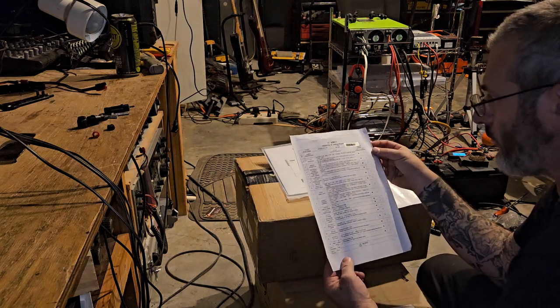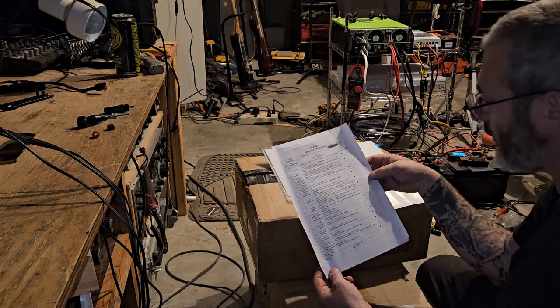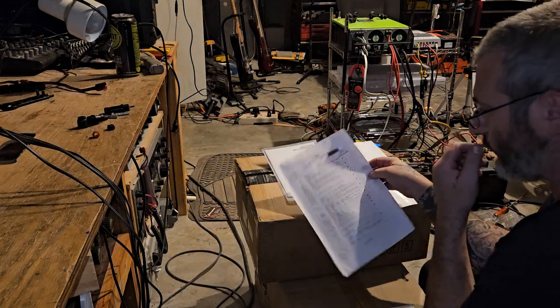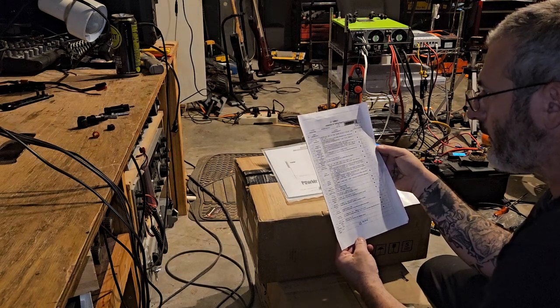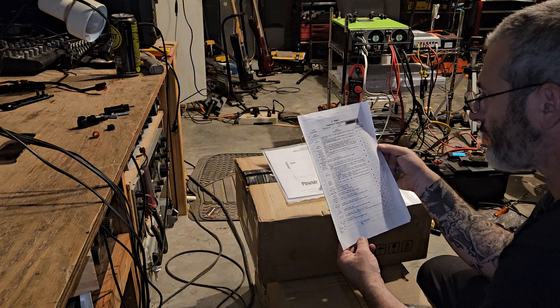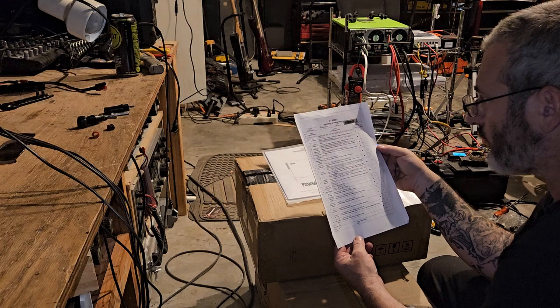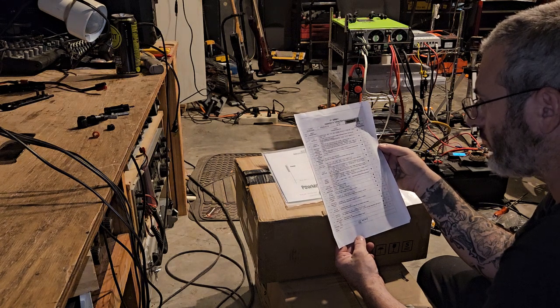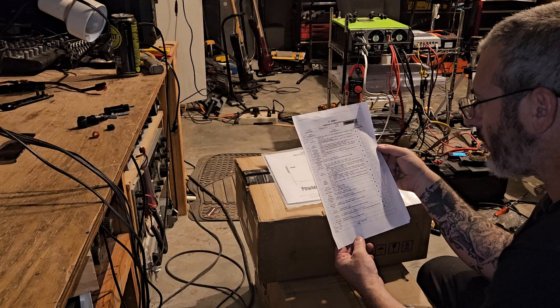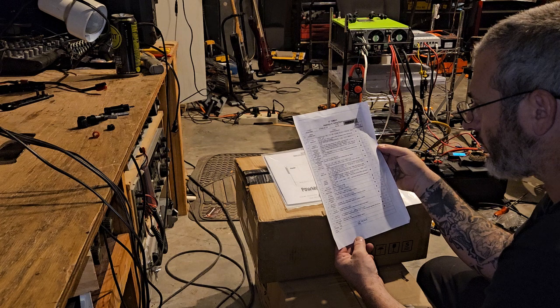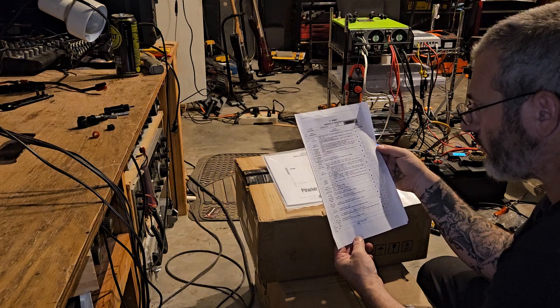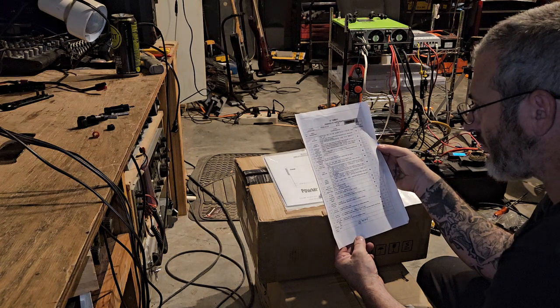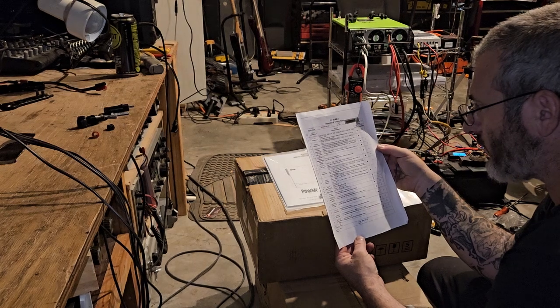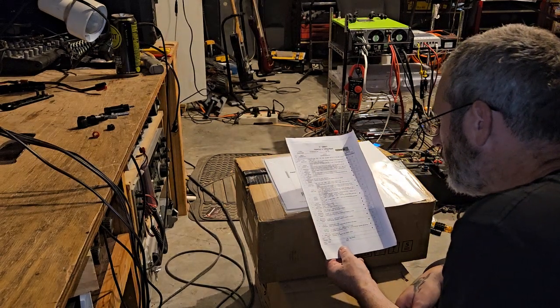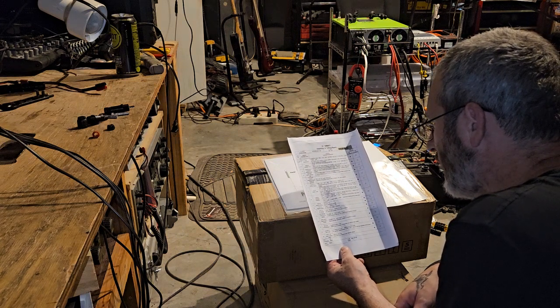They give you this inspection and testing report, and I never got this when I bought my MPP Solar HV-LV2424. So this is kind of cool. Appearance. No scratch, rust stain, or outside surface area. Nameplate is clear. Warning tips are complete. Insulation test. Apply 2,120 volts DC between DC input and AC output and earth. No arc and breakdown being detected. Leakage current less than 10 milliamps. Insulation resistance test. Apply 500 volts and insulation resistance. The result is qualified. Earth continuity test. The ground resistance of exposed conducts or components should be less than 0.1 ohm.